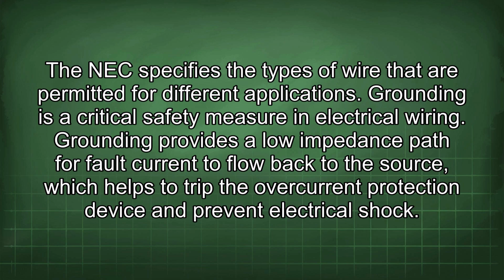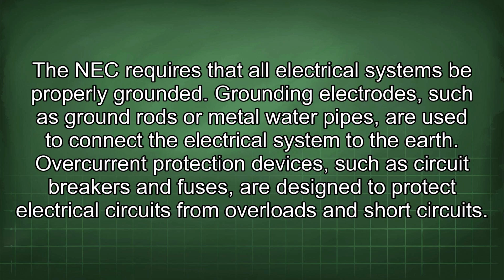Grounding is a critical safety measure in electrical wiring. Grounding provides a low impedance path for fault current to flow back to the source, which helps to trip the overcurrent protection device and prevent electrical shock. The NEC requires that all electrical systems be properly grounded. Grounding electrodes, such as ground rods or metal water pipes, are used to connect the electrical system to the earth.